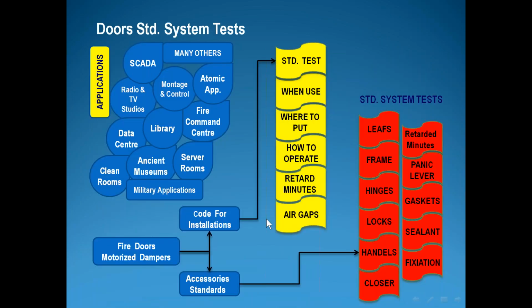So this is a summary of the doors that we will use, and we as HVAC engineers willing to design a smoke management system have to be sure that our colleagues in the fire engineering team will select the doors and the accessories of the doors, and from our side the dampers which shall be installed in the supply or return air, that these dampers shall be sealed.